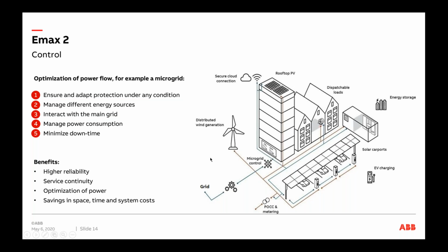Now, speaking about control, Emax 2 is embedded with a lot of technology, which allows us to use different applications in different setups. So if you're looking at adapting to certain conditions, that's possible. We look at managing different energy sources, whether it's multiple transformers or generators or whatever the energy source may be. Interaction with microgrids or, sorry, interaction with main grids: how that works, how the interface system works, how the breaker automates or makes it simple to interact with the main grid. And then we have power consumption.